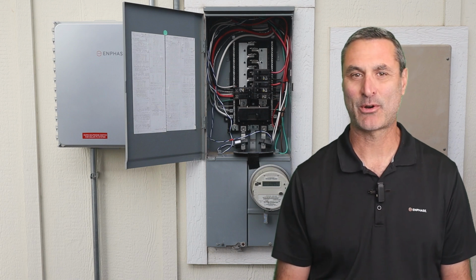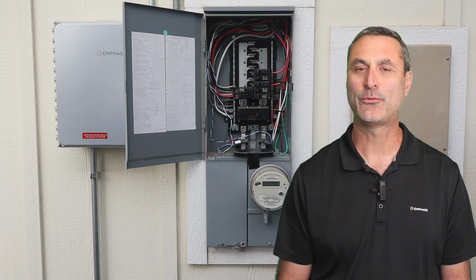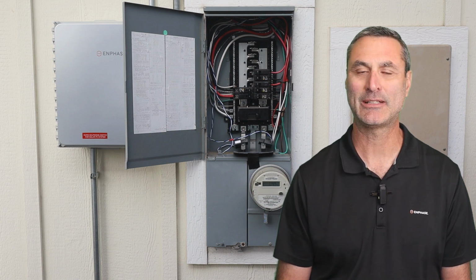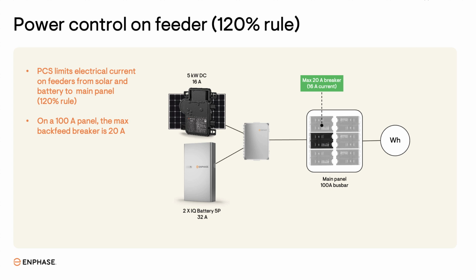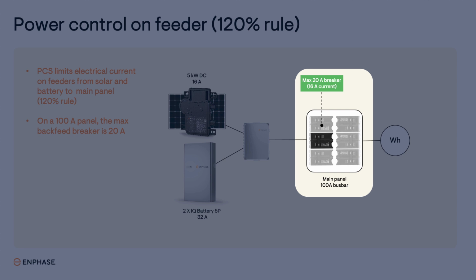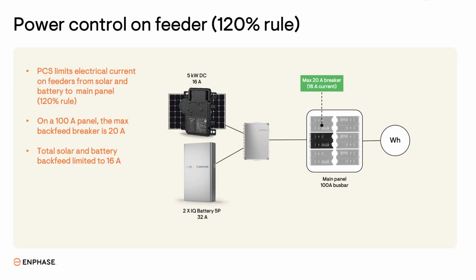Before this new feature of Busbar Overload Control was released, we could still avoid panel upgrades by using power control to limit electrical current on the feeders from solar and battery to the main panel to comply with the NEC 120% rule. For example, with a 100 amp main panel, which is common in older homes, the maximum backfeed breaker rating would be just 20 amps. That restricted the combined output of solar and the battery to just 16 amps. So, even if the homeowner had a larger solar and battery system with a higher rating than 16 amps, it would be limited to 16 amps by PCS. This could reduce potential savings for the homeowner.